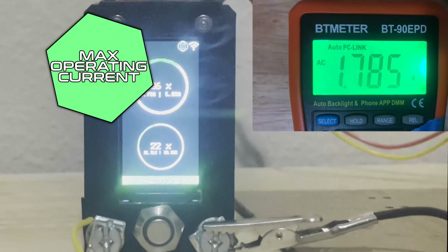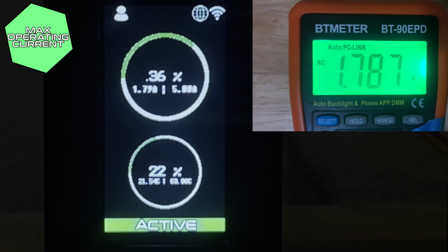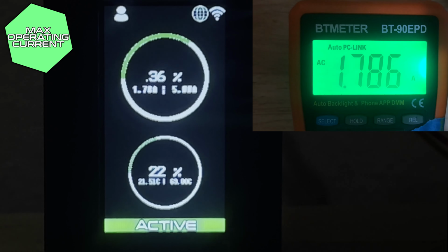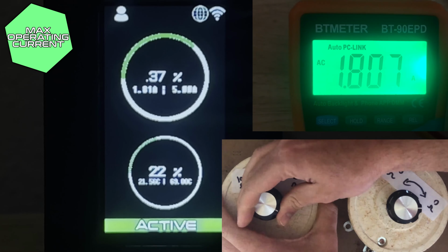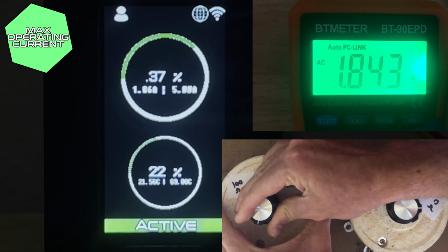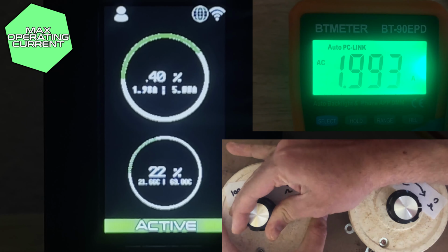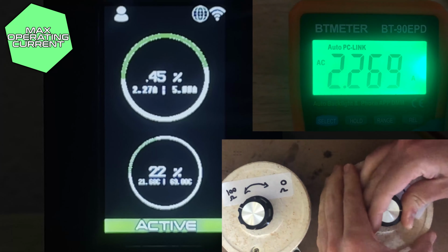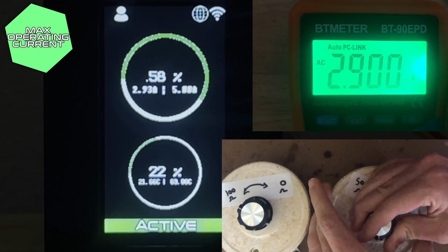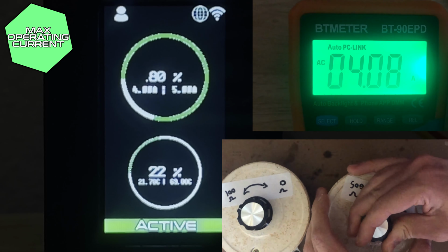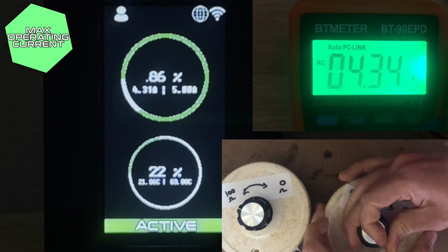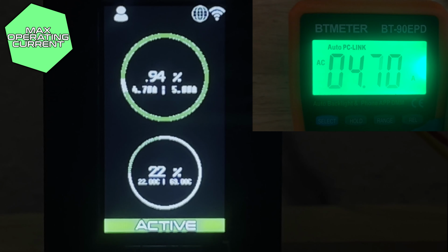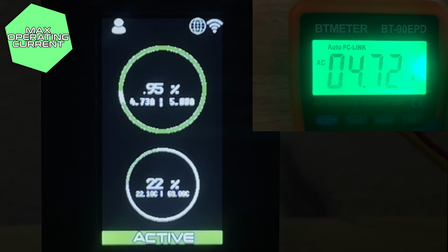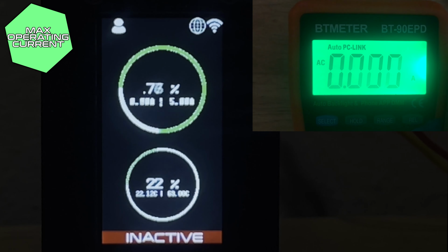Alright, so now we're going to showcase the max operating current. So I have the threshold set to 5 amps, so once 5 amps is exceeded, the breaker will automatically trip, and we're going to cover the entire scope all the way from 1.7 amps to 5 amps by just turning the potentiometers, lowering the resistance, thus increasing the supply current going to these loads. As we can see, keep spinning them. Current is increasing, it's increasing. And once we've exceeded 5 amps, the breaker will automatically trip.